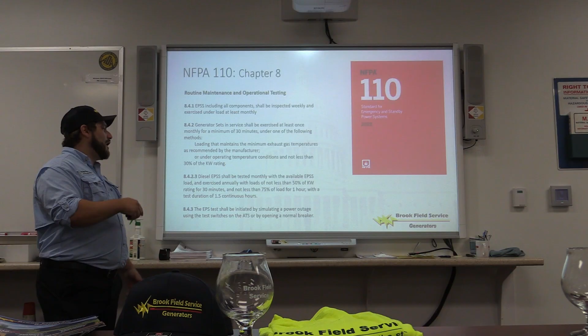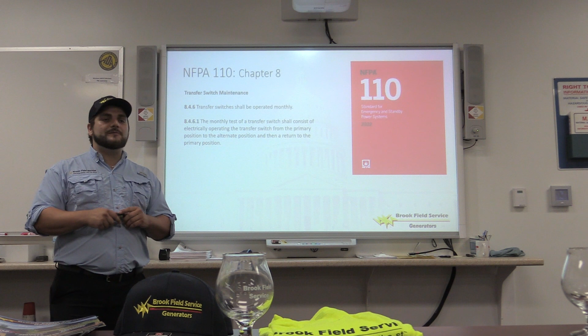Your EPSSs should include all components. The EPSS shall be initiated by simulating power outages and using the test switches on the ATS or by opening a normal breaker. So again, just making sure that the ATS is transferring over. Transfer switch maintenance, which you just alluded to, shall be operated monthly. The monthly test of a switch shall consist of electronically operating the transfer switch from the primary position to the alternate position and then a return to that primary position.